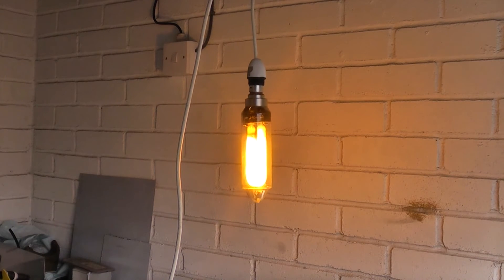I've measured the voltage across the lamp with a multimeter and it's 67 volts across the lamp so the rest of that will be taken up by the ballast.